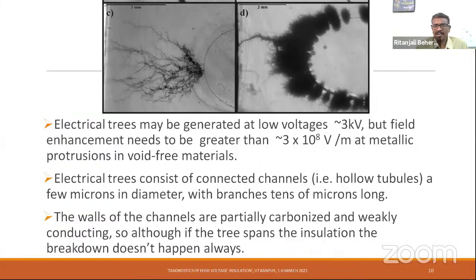Electrical trees may be generated at even a low voltage of about 3 kV, but the field needs to be high, greater than about 3 into 10 to the power 8 volts per meter at the metallic protrusions. Electrical trees consist of connected channels, as you can see from those figures.